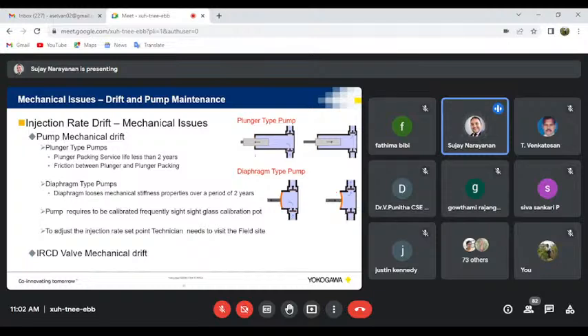If you see, this plunger is moving back and forth. It is like a piston. There is a seal over here, and there is a seal over here, if you can see. During the back and forth movement, there is a degradation in the sealing capability. So this leads to the drift in the pump.